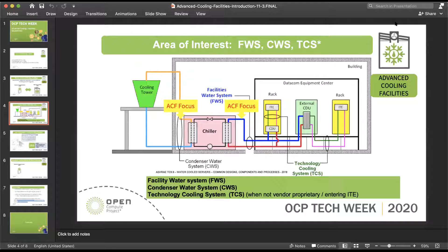So this actually captures what we're talking about in some pictures. What we have here on the side is a reference design, looking at one method of connecting to an existing cooling loop, which would be to add CDUs, coolant distribution units. You're seeing two of them, and two of everything, because in many data centers the concept of concurrent maintainability and redundancy end up being of interest.